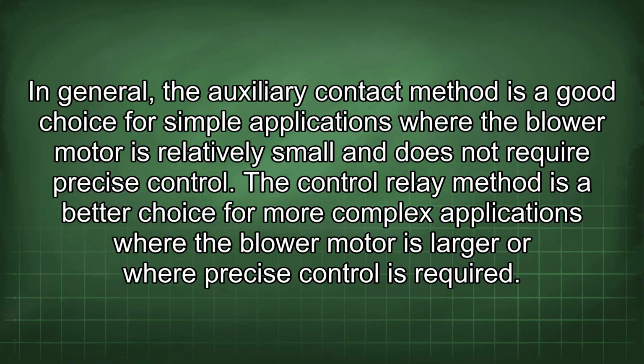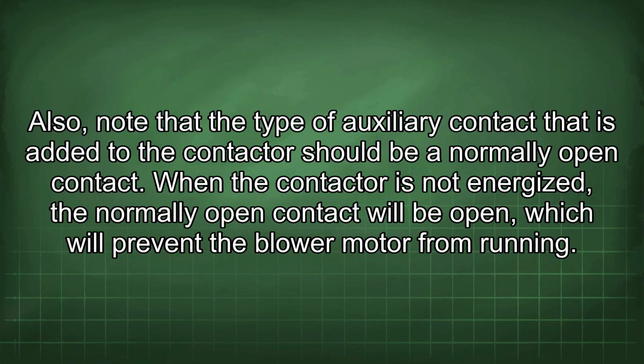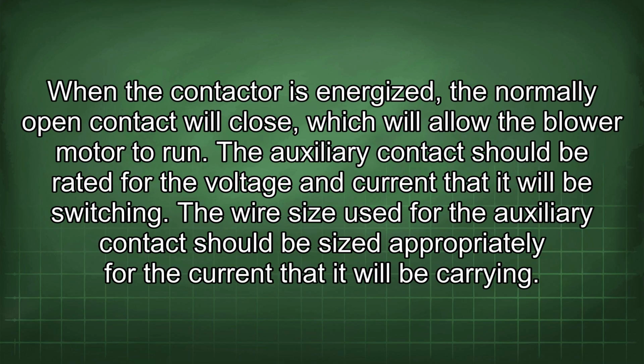precise control is required. Also, note that the type of auxiliary contact that is added to the contactor should be a normally open contact. When the contactor is not energized, the normally open contact will be open, which will prevent the blower motor from running. When the contactor is energized, the normally open contact will close, which will allow the blower motor to run. The auxiliary contact should be rated for the voltage and current that it will be switching. The wire size used for the auxiliary contact should be sized appropriately for the current that it will be carrying.